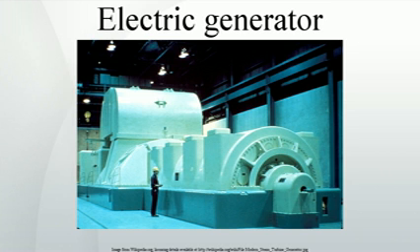Tachogenerator. A Tachogenerator is an electromechanical device which produces an output voltage proportional to its shaft speed. It may be used for a speed indicator or in a feedback speed control system. Two commonly used Tachogenerators are DC and AC Tachogenerators. Tachogenerators are frequently used to power tachometers to measure the speeds of electric motors, engines, and the equipment they power. Generators generate voltage roughly proportional to shaft speed. With precise construction and design, generators can be built to produce very precise voltages for certain ranges of shaft speeds.